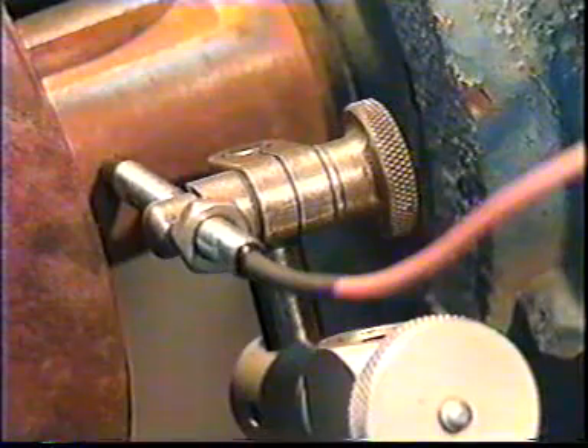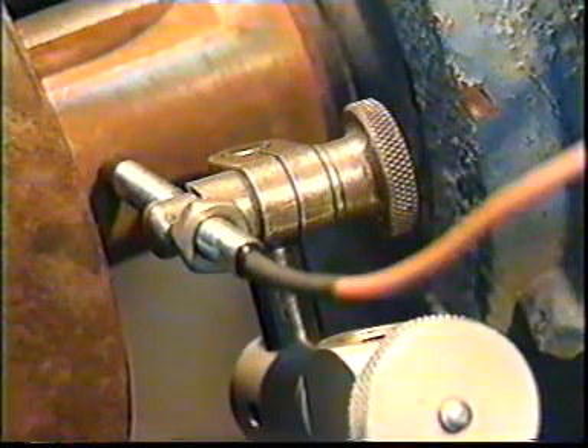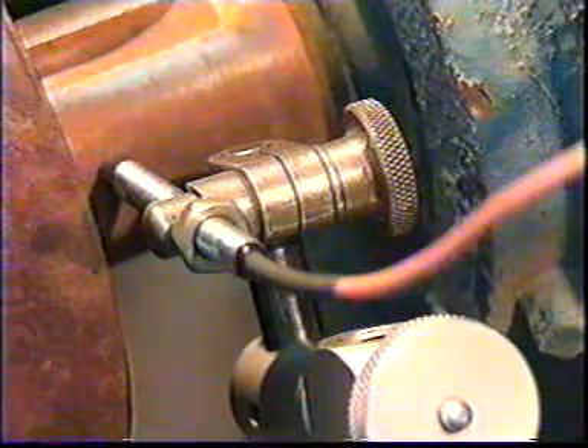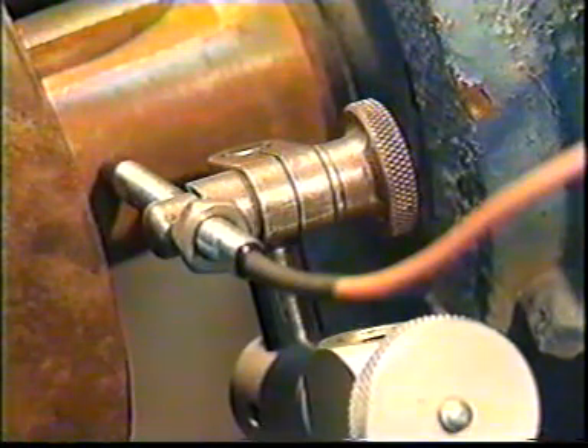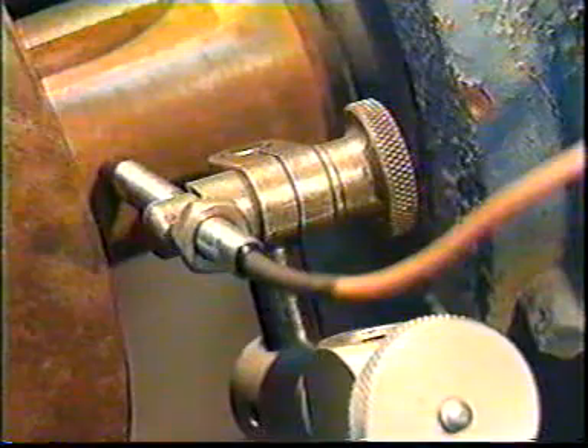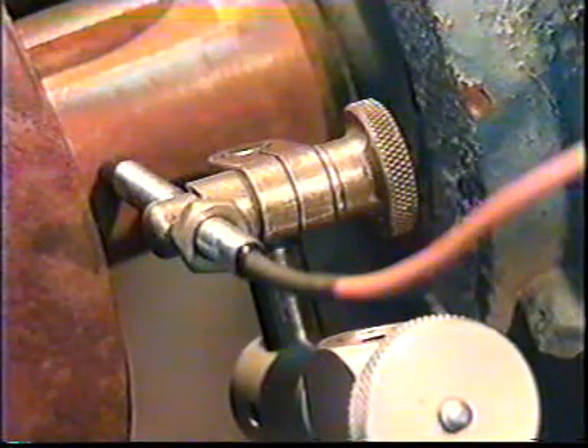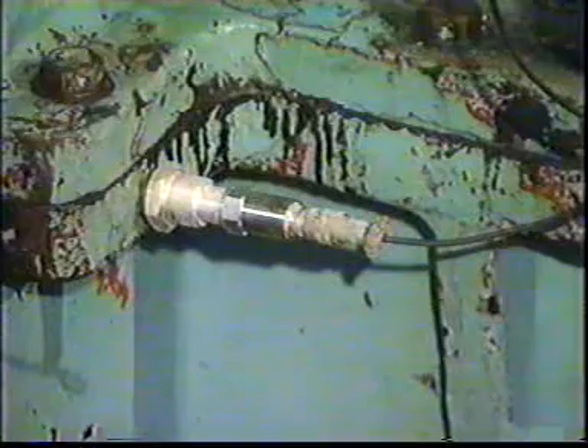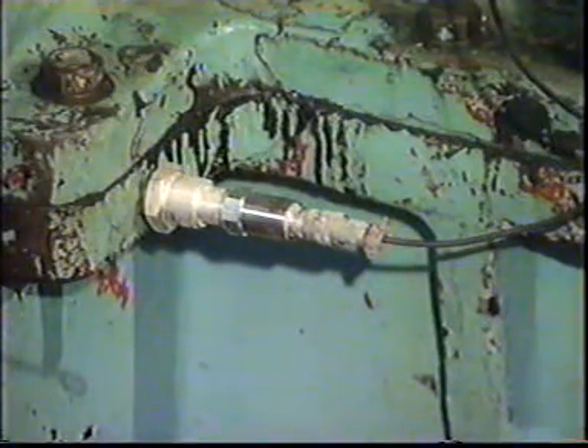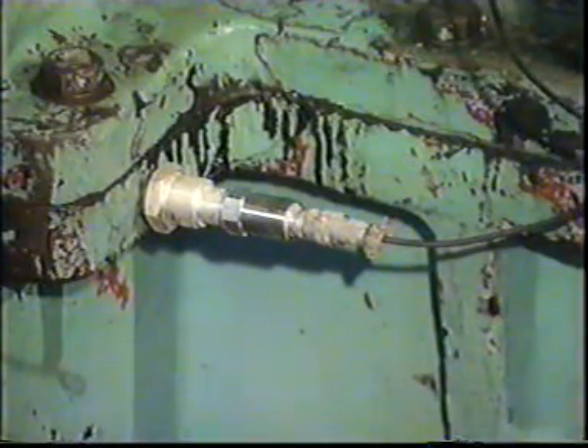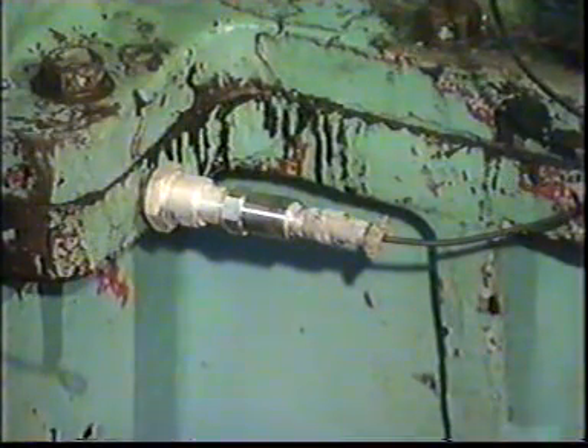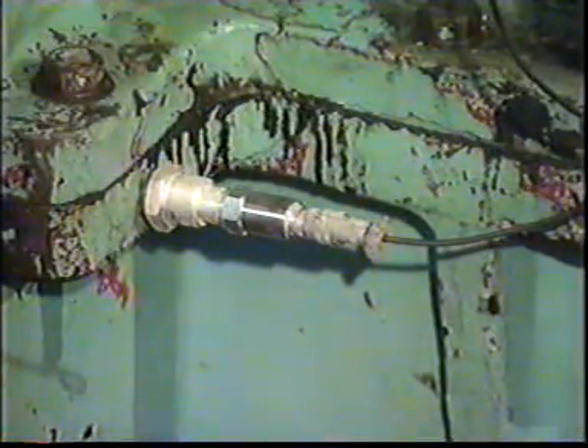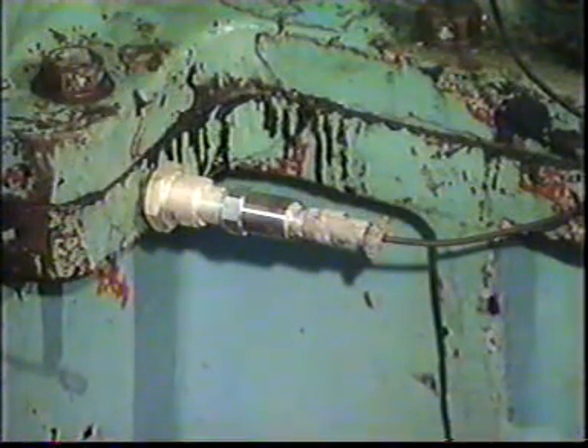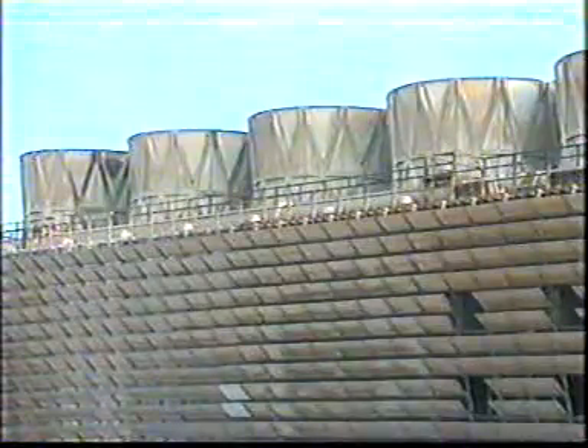A radial-mounted proximity probe may be used to measure eccentricity, which is the amount of bow or runout in a shaft. This measurement is taken at speeds of 4 to 6 RPM. Acceleration and velocity probes measure absolute or overall casing motion. The single point may provide alarms or activate a shutdown system to stop the machine before excessive vibration becomes a safety hazard. Excessive vibration can cause equipment failure, which could have catastrophic results.